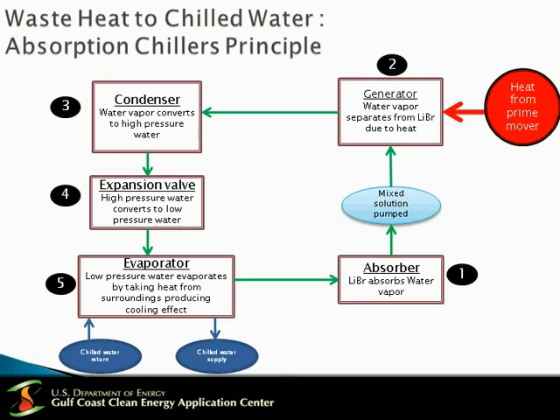the cooling effect. Now, if this were connected to a chill water loop, which is serving a building or an industrial site or a campus system, basically you can get up to 44, 46 degree chill water with the use of waste heat.